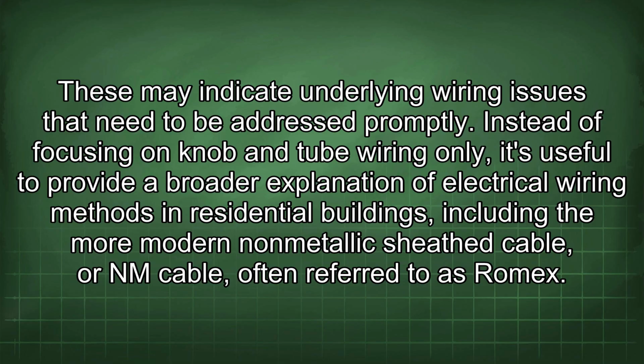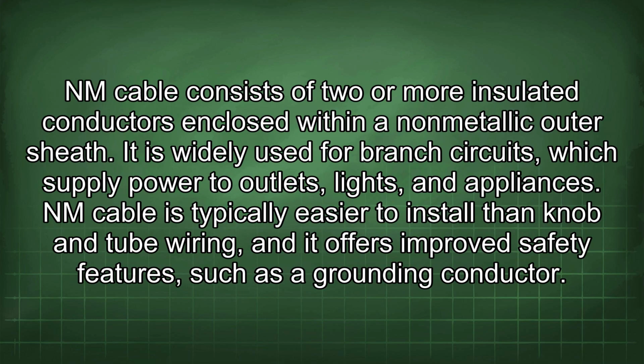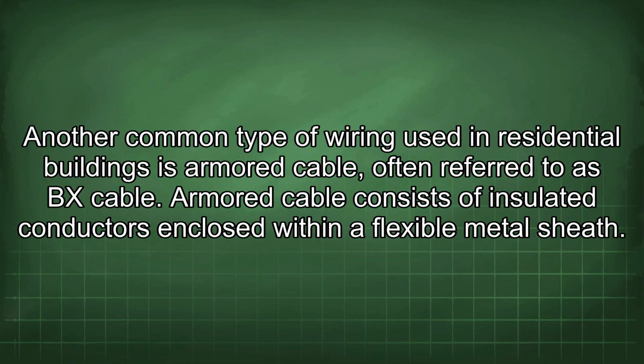Instead of focusing on knob and tube wiring only, it's useful to provide a broader explanation of electrical wiring methods in residential buildings, including the more modern non-metallic sheathed cable, or NM cable, often referred to as Romex. NM cable consists of two or more insulated conductors enclosed within a non-metallic outer sheath. It is widely used for branch circuits, which supply power to outlets, lights, and appliances. NM cable is typically easier to install than knob and tube wiring, and it offers improved safety features, such as a grounding conductor.